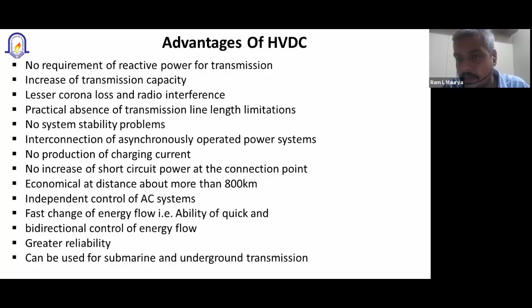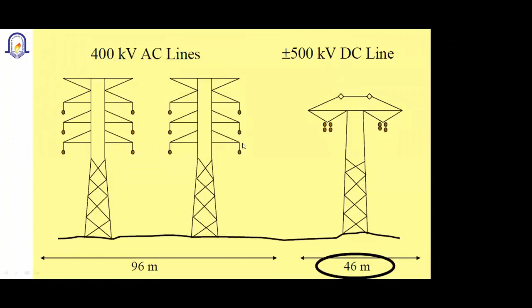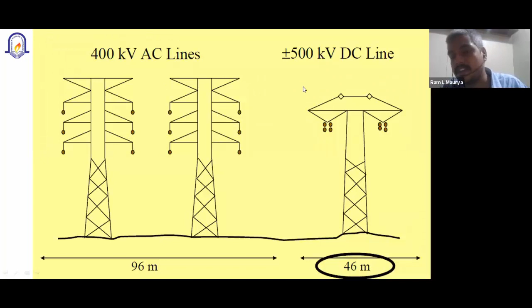There is no limit on line length, and even undersea cables can be laid in HVDC. As you can see, the same infrastructure, a 400 kV AC infrastructure and a similar plus minus 500 kV infrastructure, will carry approximately the same amount of power, as you can see on the screen. So this is the power of HVDC, power electronics.